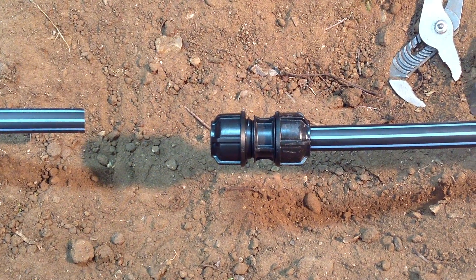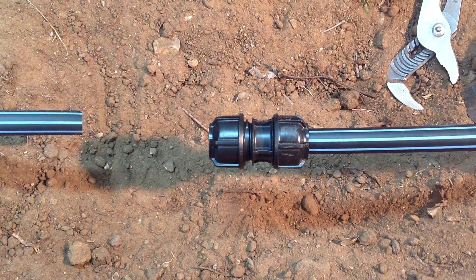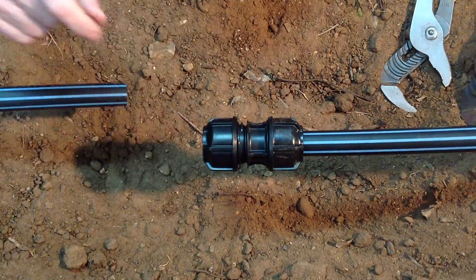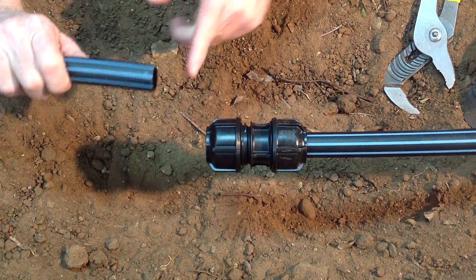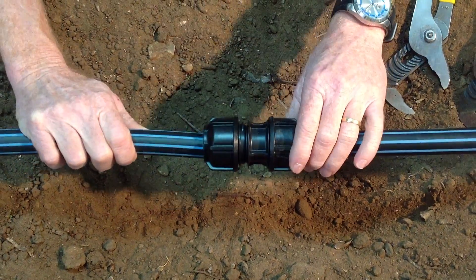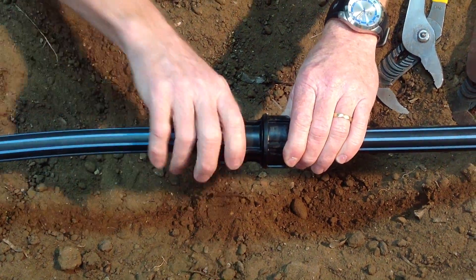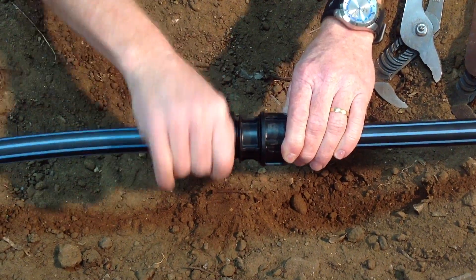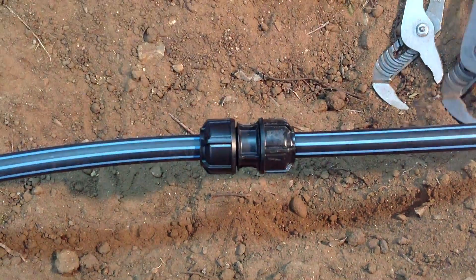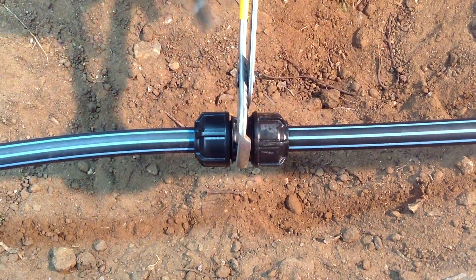What we're going to demonstrate now is how to join metric pipe to a Philmac 3G metric connection. Simply ensure that there are two to three threads showing on the body. Ensure that the pipe face is cut square and clean, and then push the pipe up until the first point of resistance. Tighten by hand and then all the way to the flange using a wrench.